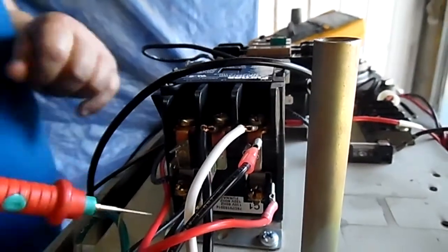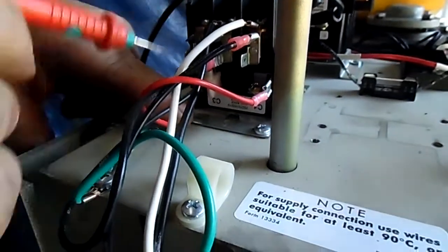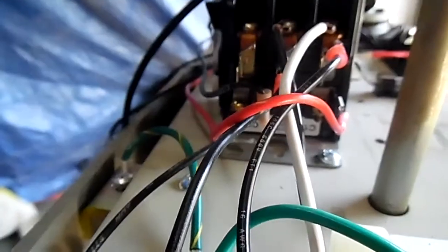With the contactor, if they're 120 volt, whatever your power is on these two leads, Hobart usually jumps number two directly to the coil.